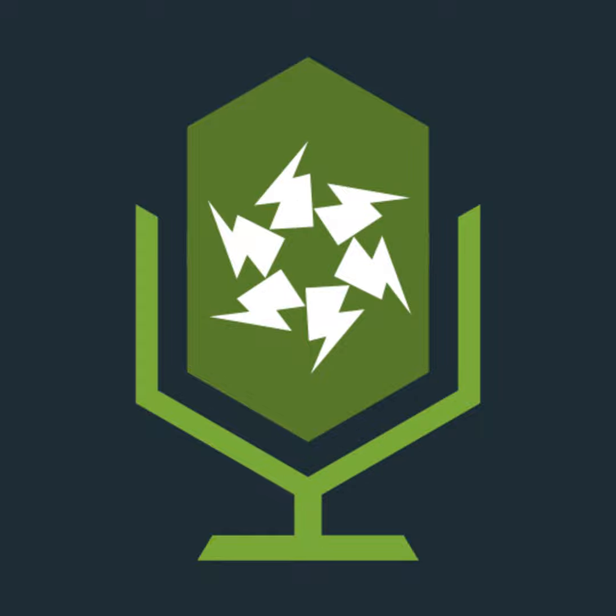And we mentioned electrical separation earlier on. We said that you can't put more than one item of equipment on one isolation transformer in case you created loops between the two bits of equipment. You can do that with generating sets, for example, but it is a special scenario, and that is in 418.3.